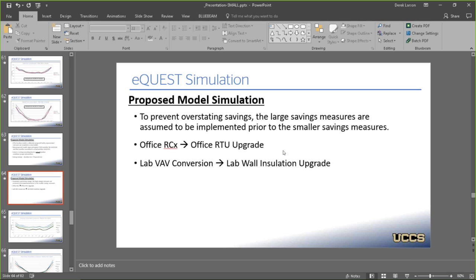I don't, but you could conceivably drop a kW or two at each VAV. And that is something that could be done if they choose to move forward on that option, and we do a full final design of the new system, then that is something we could consider. So you can replace this equipment up there in Washington, which I know has a strict energy code, and they won't make you go back and fix this insulation deficiency first?